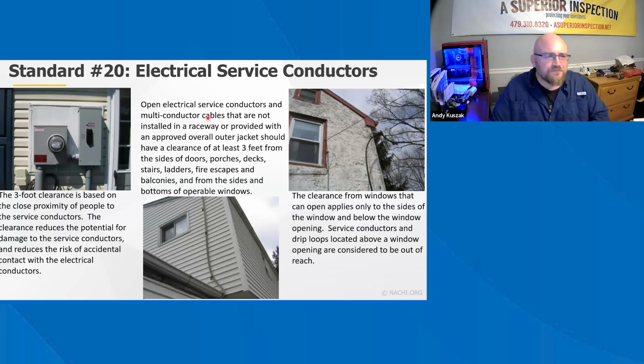Electrical service conductors. So we're going to start over here on the left. That 3-foot clearance is based on close proximity of people to the service conductors. The clearance reduces the potential for damage to the service conductor and reduces the risk of accidental contact with the electrical conductors. Open electrical service conductors, like the one you see in the picture, and multi-conductor cables that are not installed in a raceway or provided with an approved overall outer jacket should have a clearance of at least 3 feet from the sides of doors, porches, decks, stairs, ladders, fire escapes, and balconies, and from the sides and bottoms of operable windows.